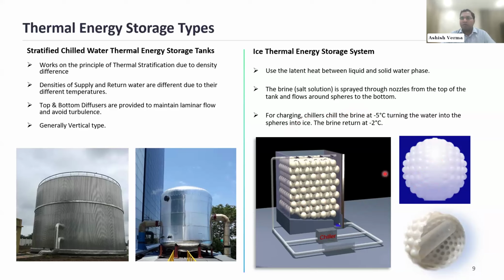Nowadays we have multiple generations of this ice-based thermal storage. The newest generation has this ice air capsule here, which helps in expansion and contraction as the ice is formed inside the ball. Another form is phase change material, which is in between the chilled water thermal energy storage tank and the ice-based system. The advantage of PCM is that it occupies less space compared to chilled water, but it has limitations in terms of the temperature at which it can operate. There are two types, negative and positive. I will not cover it right now.